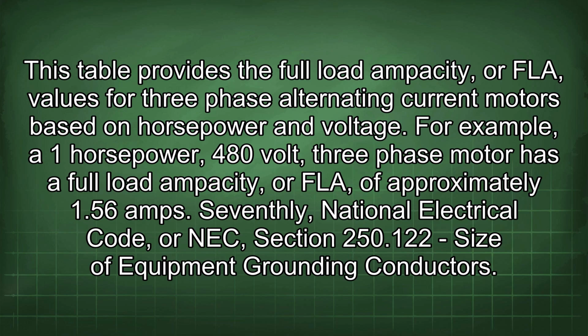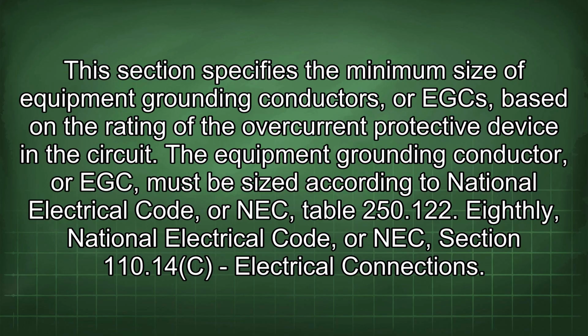Seventhly, NEC Section 250.122 Size of equipment grounding conductors. This section specifies the minimum size of equipment grounding conductors, or EGCs, based on the rating of the overcurrent protective device in the circuit. The equipment grounding conductor, or EGC, must be sized according to NEC Table 250.122.